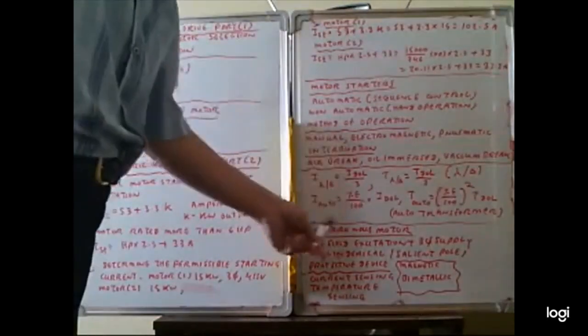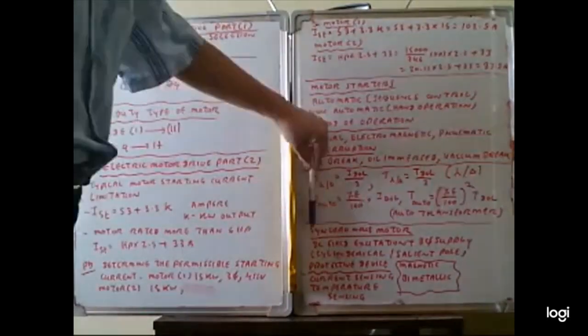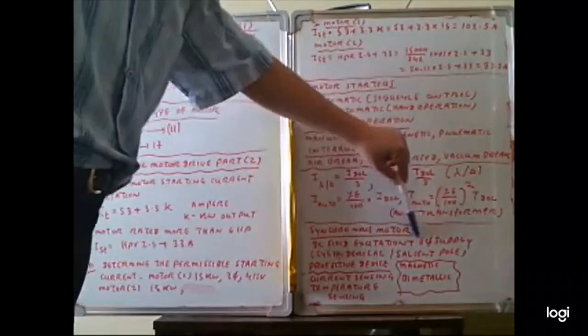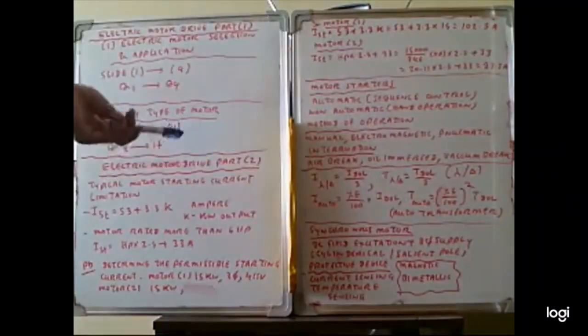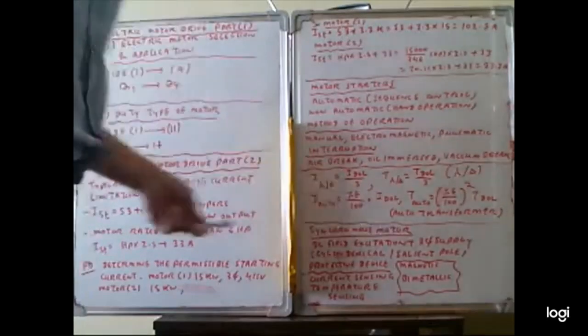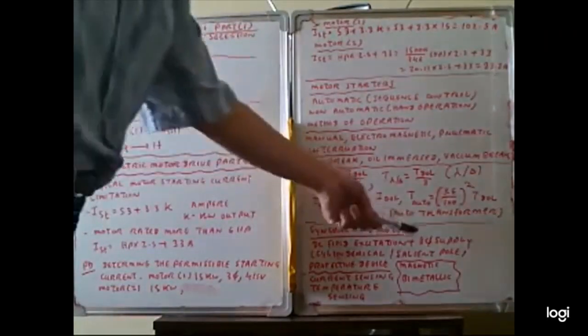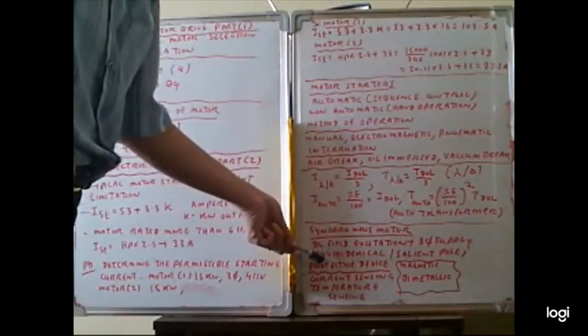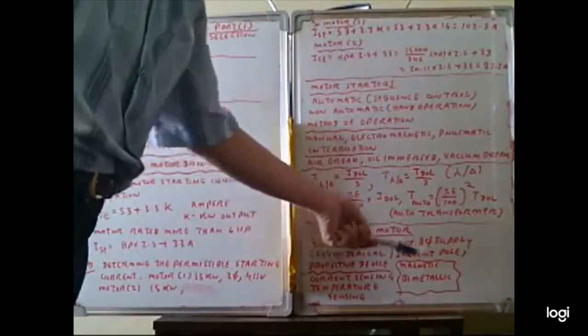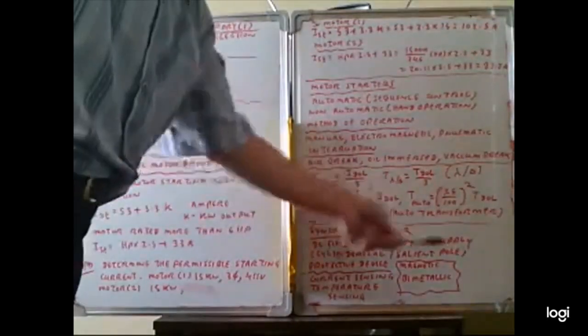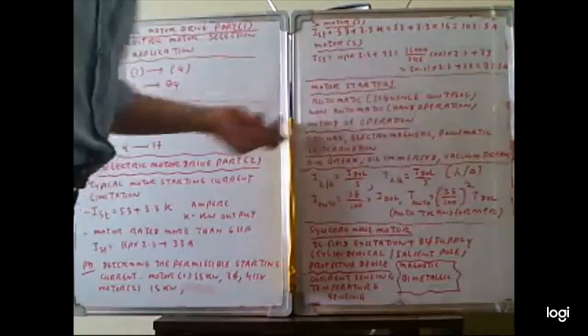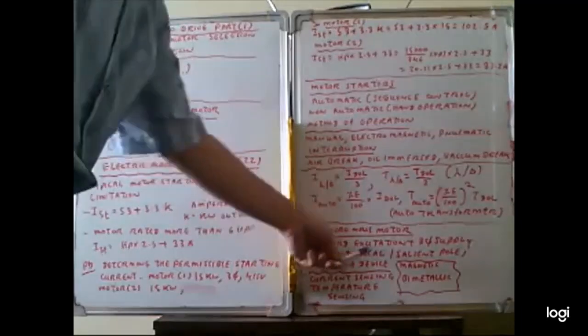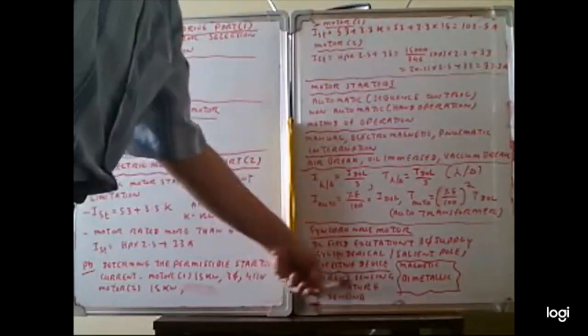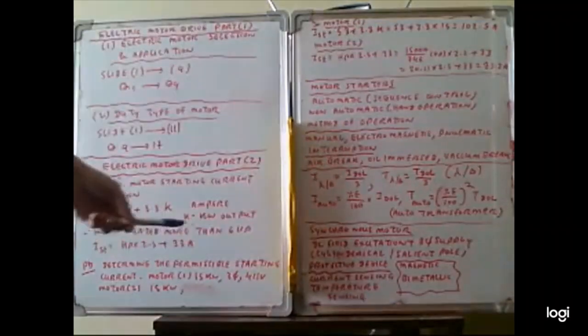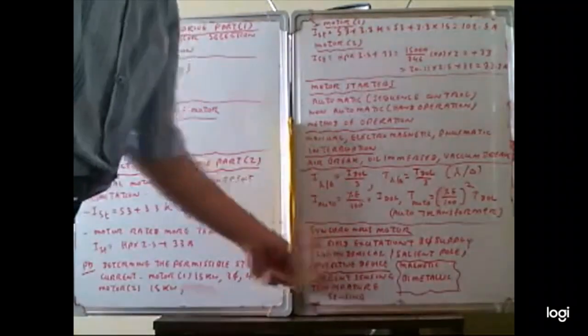We can also utilize the synchronous motor. The synchronous motor's basic construction is DC field excitation plus three-phase supply, so two supplies are supplying the motor. The DC is supplied by a DC generator, and the three-phase supply is supplied by the three-phase supply system. There are two typical constructions, salient pole and cylindrical rotor machines. Synchronous motors are utilized because they can vary the power factor. The protective devices utilized are current sensing devices and temperature sensing devices. When the current in the motor is higher or the temperature is higher, the sensing device can switch off the motor.